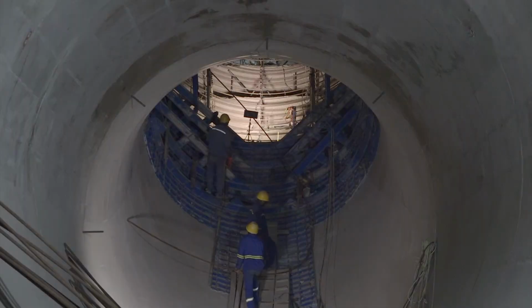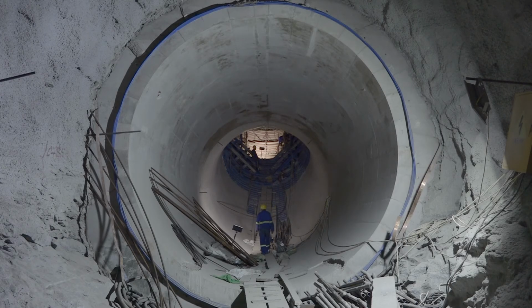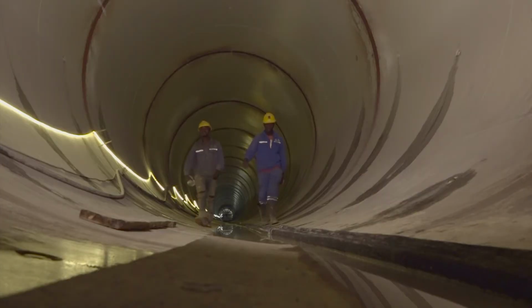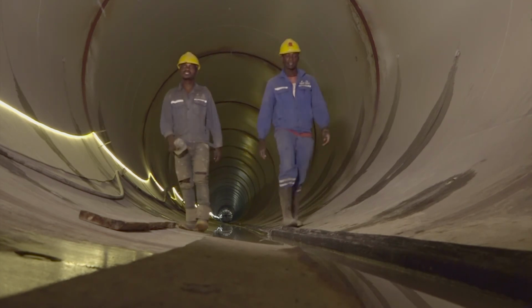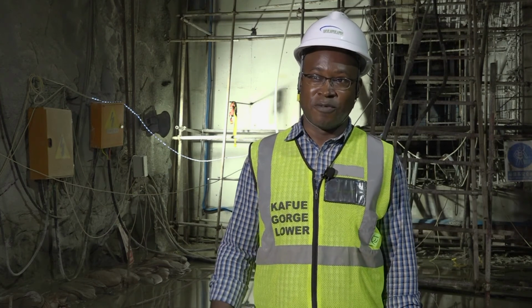We have the horizontal part, which we call the low pressure part, then vertical shafts, and the lower horizontal part, which is where we are. On average, each of the 5 power tunnels has a length of 647 meters, from the surge shaft up to the main inlet valve (MIV) at the powerhouse. Of this 647 meters, about 312.5 meters is steel, as the power tunnels enter the MIVs.